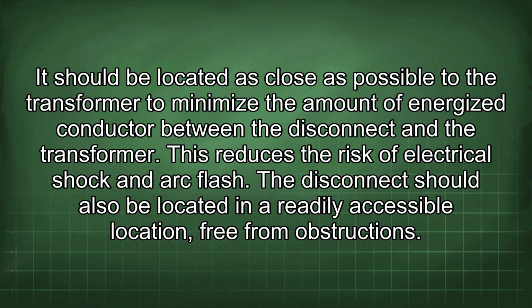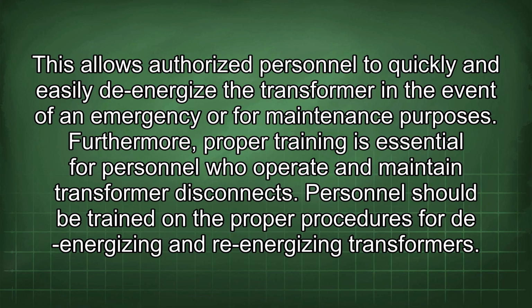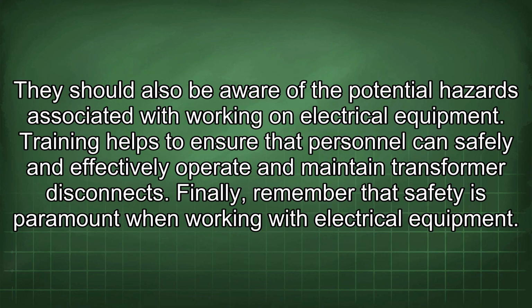The disconnect should also be located in a readily accessible location free from obstructions. This allows authorized personnel to quickly and easily de-energize the transformer in the event of an emergency or for maintenance purposes. Furthermore, proper training is essential for personnel who operate and maintain transformer disconnects. Personnel should be trained in the proper procedures for de-energizing and re-energizing transformers. They should also be aware of the potential hazards associated with working on electrical equipment. Training helps to ensure that personnel can safely and effectively operate and maintain transformer disconnects.